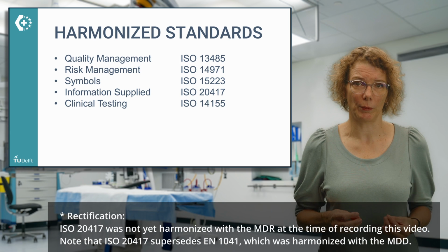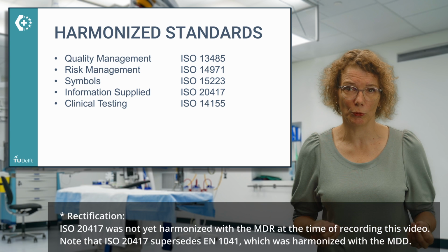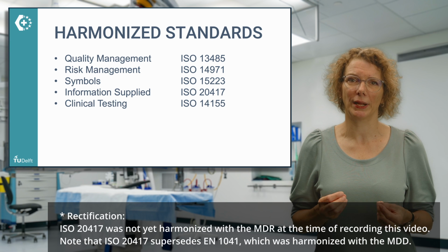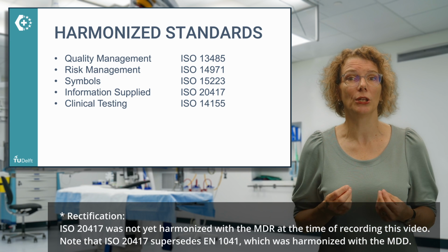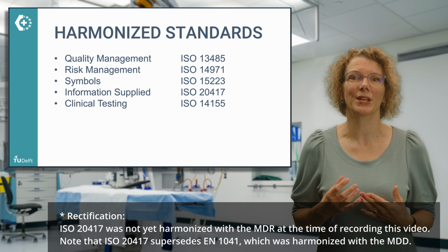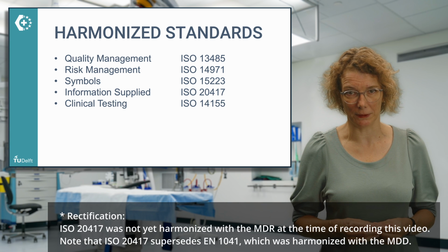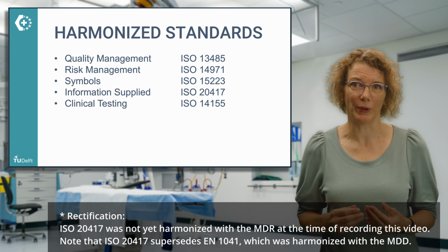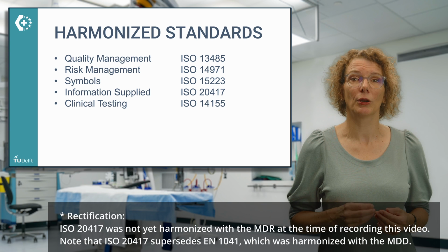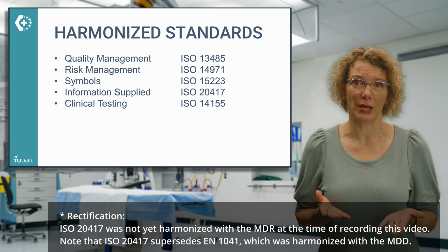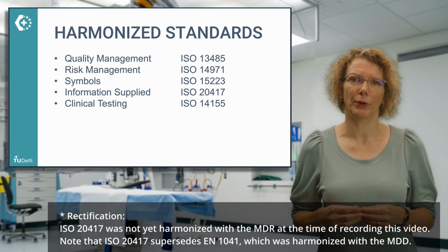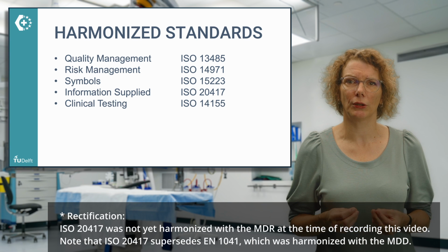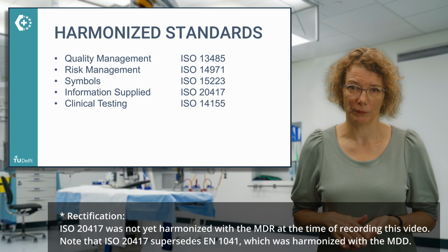Standards that are harmonized with the MDR provide manufacturers with a means to assume conformity with the requirements when following these standards. However, application of these harmonized standards is formally not obligatory, as long as appropriate evidence is provided to demonstrate conformity. In earlier parts of this course, we already referred to a couple of relevant harmonized standards for quality management, risk management, and for the information supplied with the device. In another part of this course, we will tell you more about the MDR's expectations on risk management and on clinical research, and the accompanying standards.